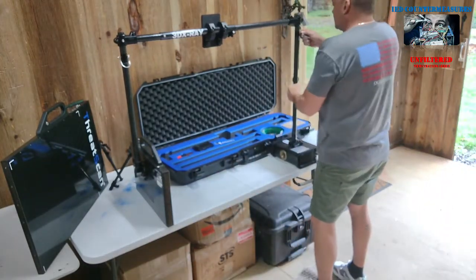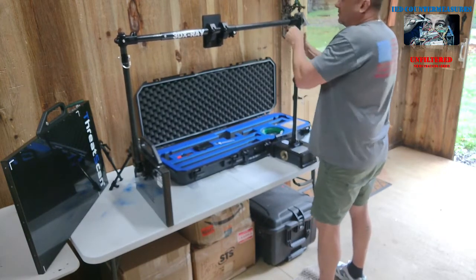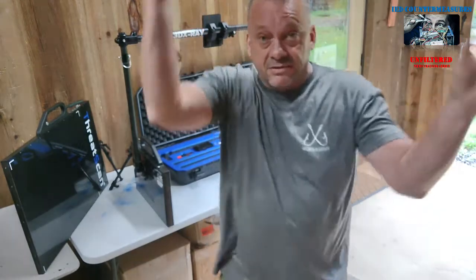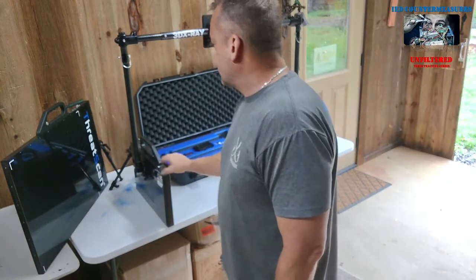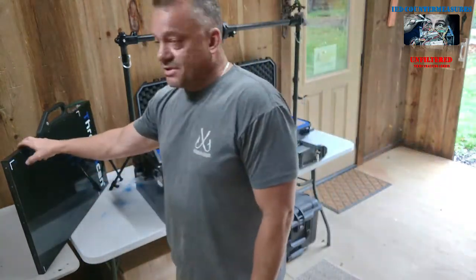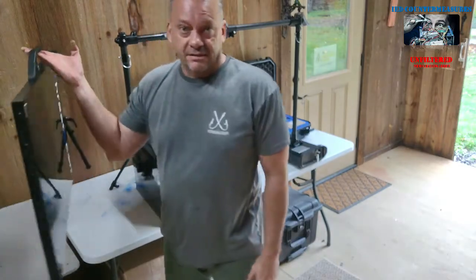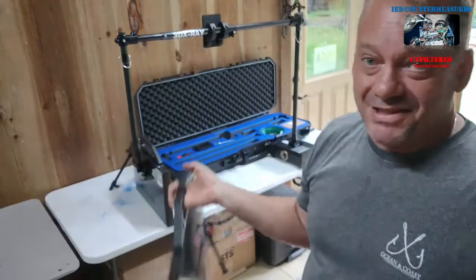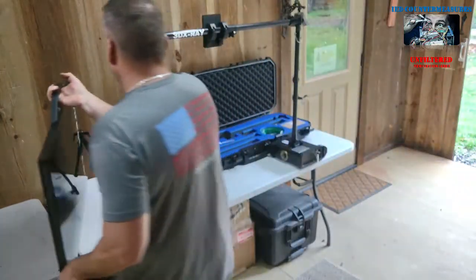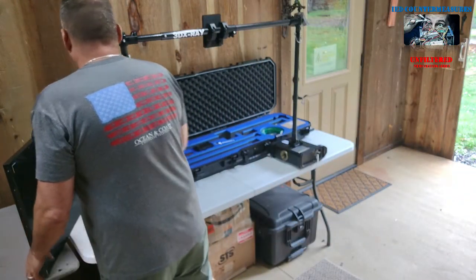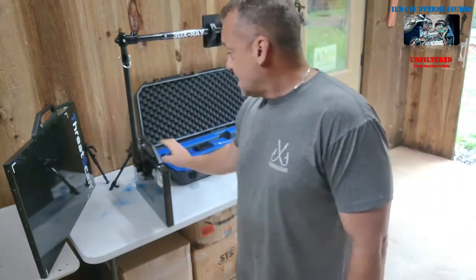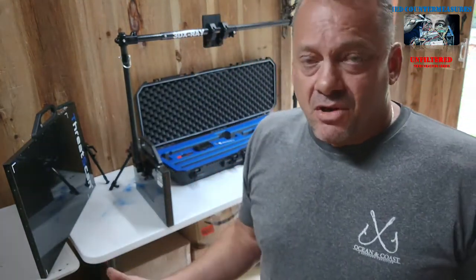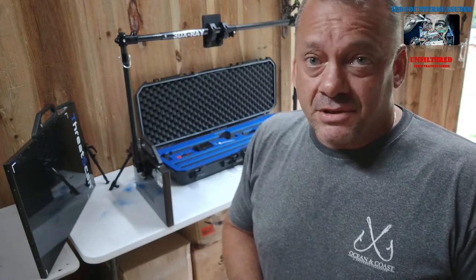You can also do above-ground scans with this system because it can be lifted up at different angles, depending on your robot arm's strength. Because it's so light, this complete system with this panel is around 25 to 26 pounds. This one shoots up just a little more—believe it or not, this panel is ridiculously light for how big it looks. I think it only goes up to around 30 pounds with the larger panel, but honestly, I like using the LS3 panel because it's smaller and easier to move around.